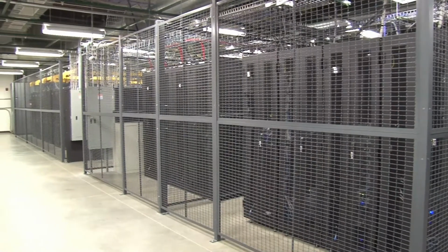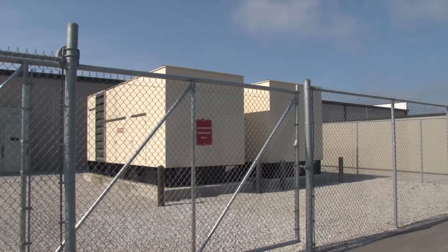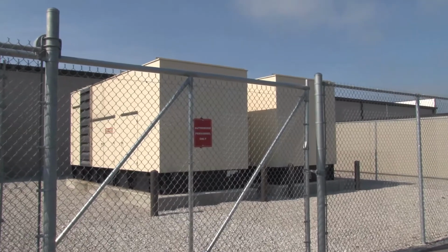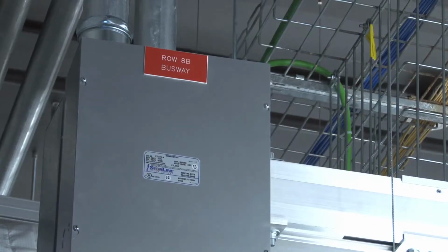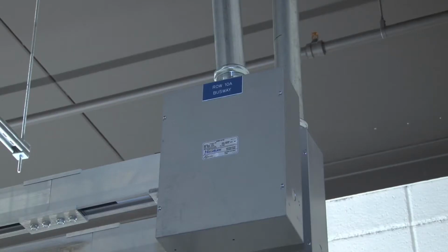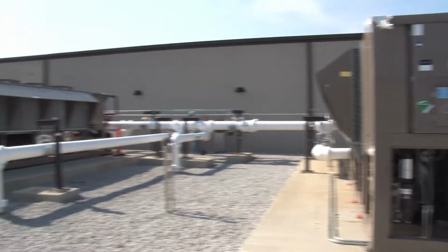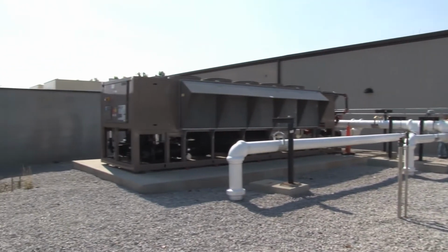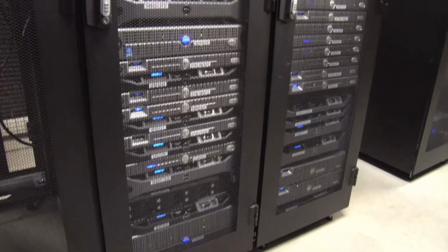Involta is a multi-tenant data center provider. We have 7 data centers across the country in secondary markets. The Involta Tier 3 data centers have redundant diesel generators, redundant electrical supply to the equipment, and redundancy with respect to all the cooling. A Tier 3 data center brings up the concept of concurrently maintainable, where you could take a piece of equipment out of service so as to maintain it without reducing the ability to serve cooling, electrical, or other physical environments.